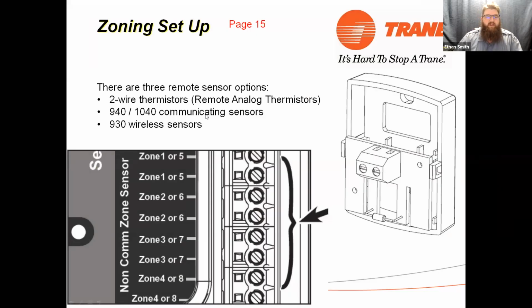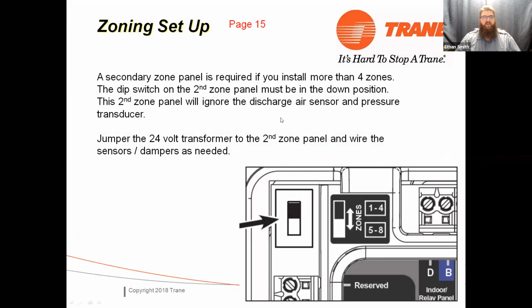Okay. The RATs we talked about are just 2 wire RATs. This is a little thermistor. This is about a 1-inch square white box that you mount to the wall. 2 wires, and they just wire up to your zone panel. Not polarity sensitive. If you're putting in that second zone panel, so you've gone contrary to my advice and gone into more than 4 zones, there is a switch in the top right or top left-hand corner of that zone panel to switch it from zones 1 through 4 to 5 through 8. It is important that you do that and pick the right panel.